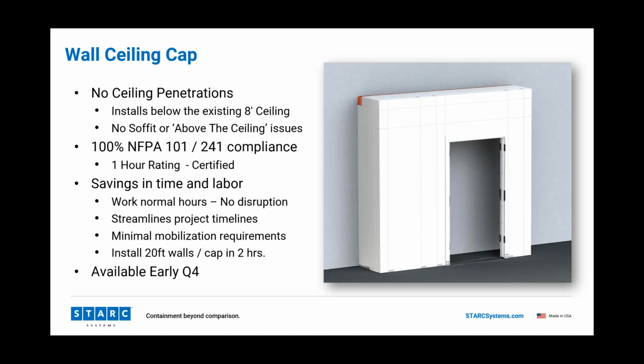We've learned the holy grail in temporary containment, when we're out talking to customers, is to stay below the ceiling while providing that 1 hour rated barrier. So we've developed a system, which is our number one request, to put a cap on our fire block walls, allowing fast, dustless, and quiet creation of a fire containment along a rated wall. When you add a door and negative air capability, these walls can serve as a rated anteroom or working space, so that you can penetrate the adjacent wall during the process.